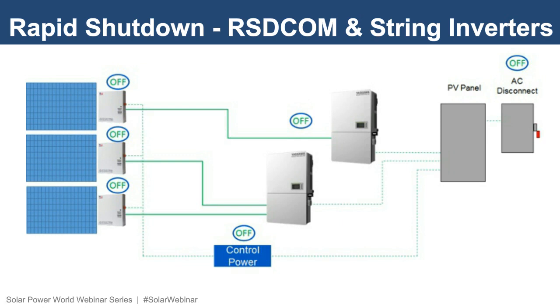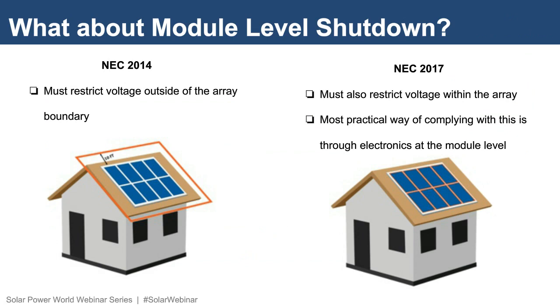Early adopting state, or you have a client that already wants to comply with module-level shutdown. What can you do? What solutions do you have? Well, again, to reiterate, the requirement of 690.12(B)(2) is not officially effective until January 1st, 2019. That means today, even in 2017 jurisdictions, array-level rapid shutdown is really where the requirements end.